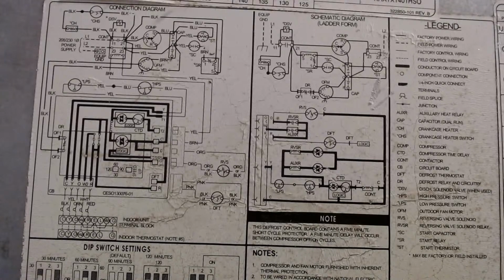Okay. Now let's follow our reversing valve, which is our O terminal. It comes up and comes over in two different branches. All right. I'm going to take the right branch and follow over here to O. And you can see over here, it goes through the board as well. And it also hits our R terminal for our DFT, which is our defrost time sensor.